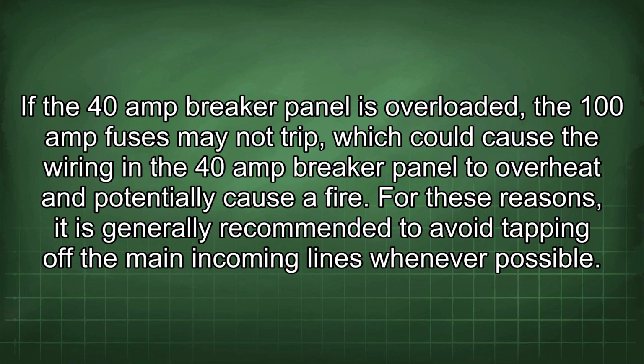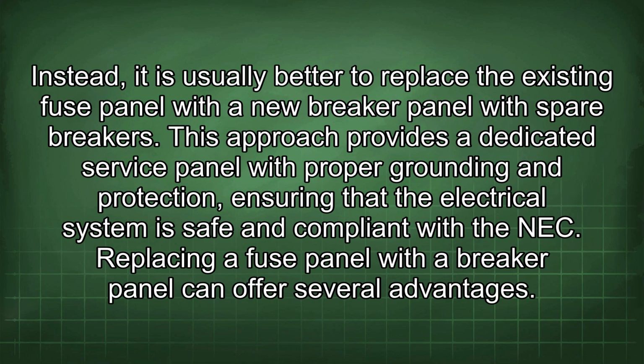For these reasons, it is generally recommended to avoid tapping off the main incoming lines whenever possible. Instead, it is usually better to replace the existing fuse panel with a new breaker panel with spare breakers. This approach provides a dedicated service panel with proper grounding and protection, ensuring that the electrical system is safe and compliant with the NEC. Replacing a fuse panel with a breaker panel can offer several advantages.